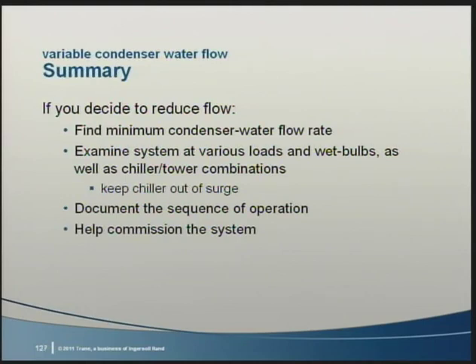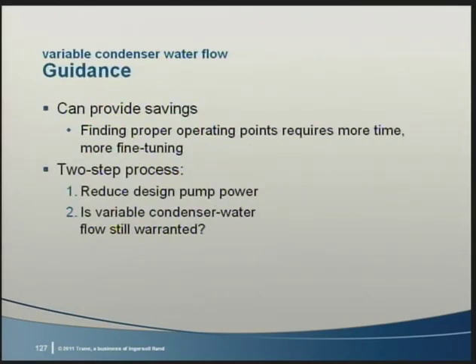The bottom line is that variable condenser water flow allows some system savings, but it takes more design examination and on-site fine-tuning to achieve those savings. We suggest that you first reduce condenser water pump power at design. You can easily do this by reducing the design flow rate. Then, determine if variable flow is still warranted.